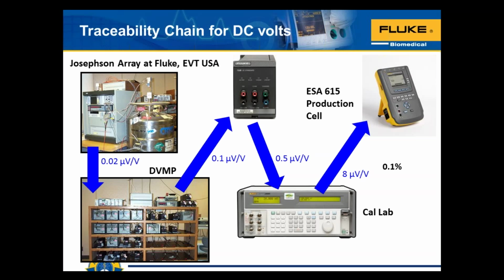From that primary volt, we transfer that to what we call transfer standards. So these would be a set of transfer standards that we use in each of the production cells in Fluke and Fluke Biomedical and other divisions of Fluke to create the test instrument that you will use from us. When we use that transfer standard, it adds to the uncertainty stack up. The uncertainty of that transfer standard brings us from 0.02 microvolts per volt to 0.1 microvolts per volt. You see how that's increasing the uncertainty? And from that transfer standard to the test instruments that might be used in a calibration laboratory, there's an additional uncertainty that brings us to 0.5 microvolts per volt for a DC volt measurement.